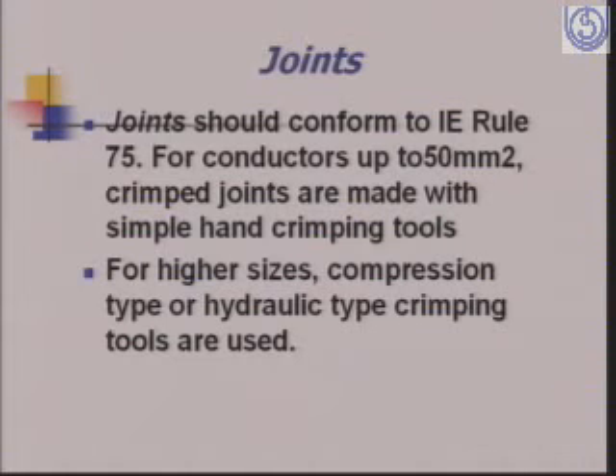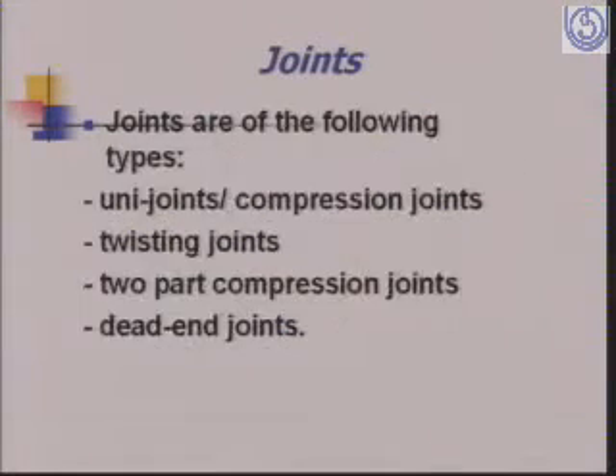For conductors up to 50 mm square, crimped joints are made with simple hand crimping tools. For higher sizes, compression type or hydraulic type crimping tools are used. The joints can be of various types: uni joints, compression joints, twisting joints, two-part compression joints, and dead-end joints.